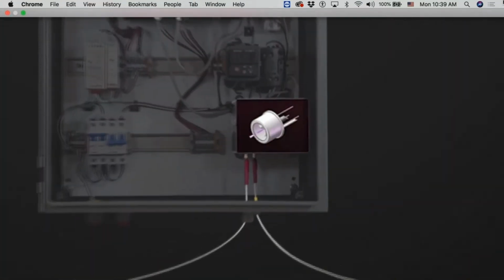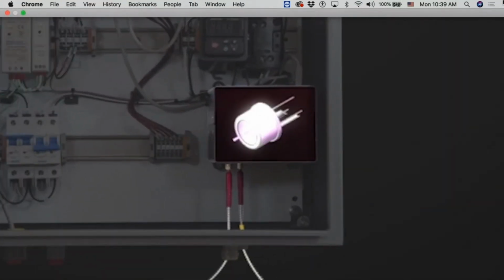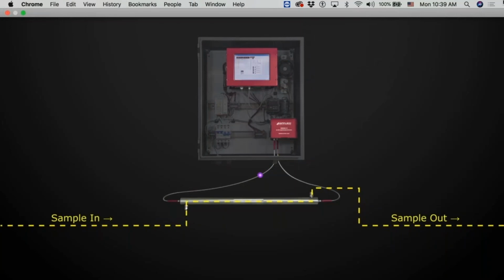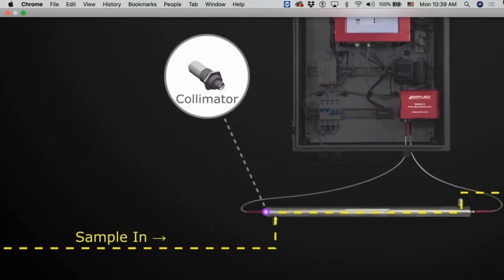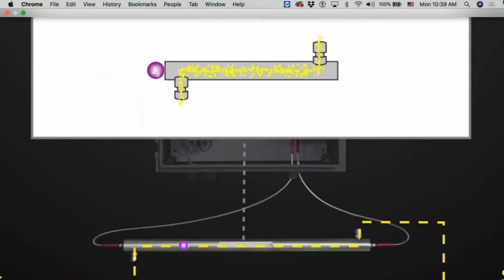During normal operation, signals of white light pulse from a xenon light source. The signal travels via a fiber-optic cable to the entry point of the flow cell, where the light beam is narrowed through a collimator lens. Here, the signal radiates directly across the flow cell path length, interacting with the continuously drawn process sample fluid flowing inside.